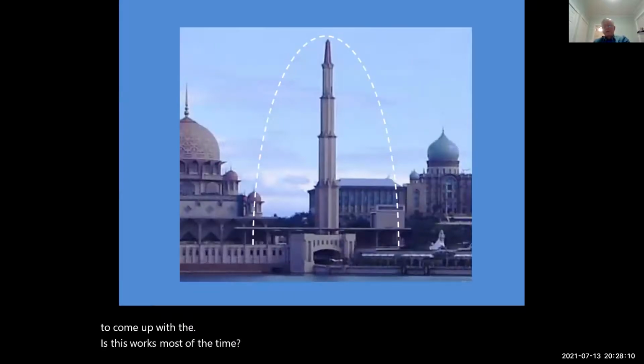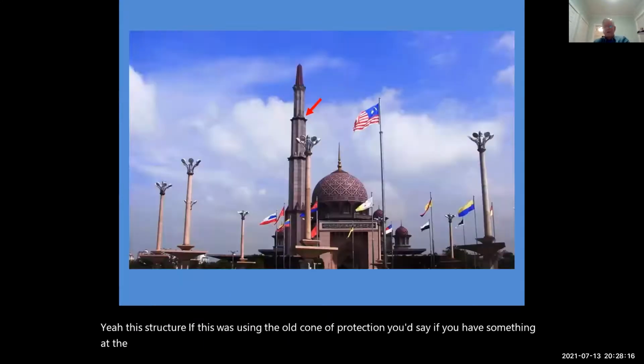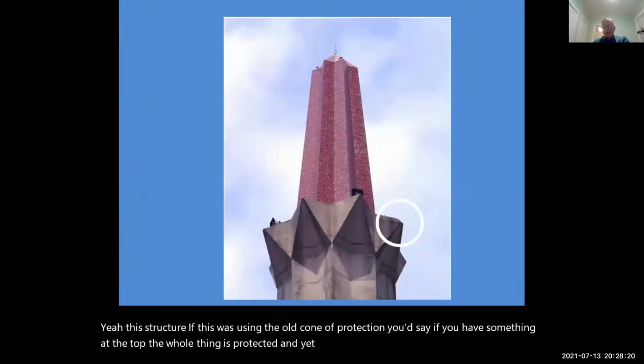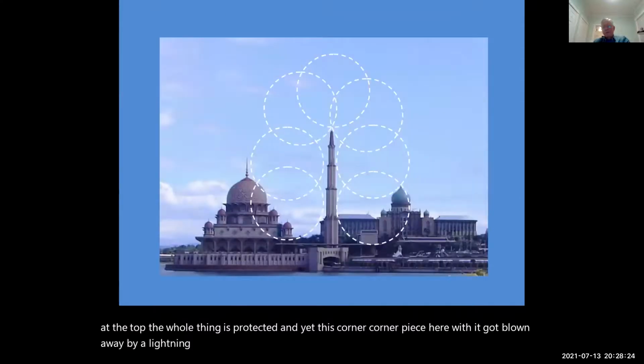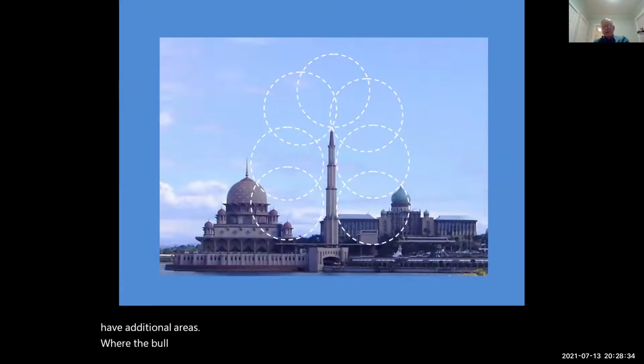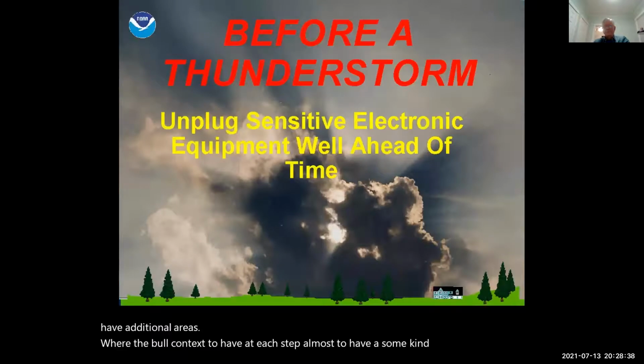This structure, if you were using the old cone of protection, you'd say, well, if you have something at the top, the whole thing's protected. And yet this corner piece here got blown away by a lightning strike. So if you follow this, you can see where you need to have additional areas where the ball contacts, to have at each step almost, some kind of air terminal.